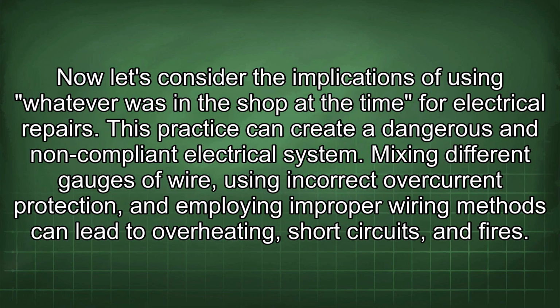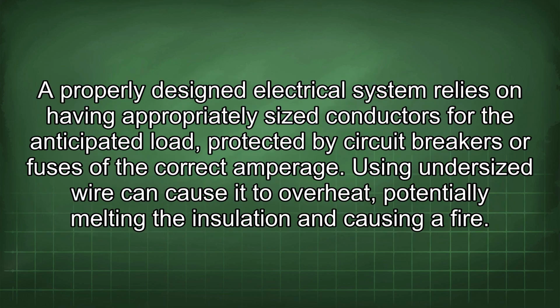Now let's consider the implications of using whatever was in the shop at the time for electrical repairs. This practice can create a dangerous and non-compliant electrical system. Mixing different gauges of wire, using incorrect overcurrent protection, and employing improper wiring methods can lead to overheating, short circuits, and fires. A properly designed electrical system relies on having appropriately sized conductors for the anticipated load, protected by circuit breakers or fuses of the correct amperage.